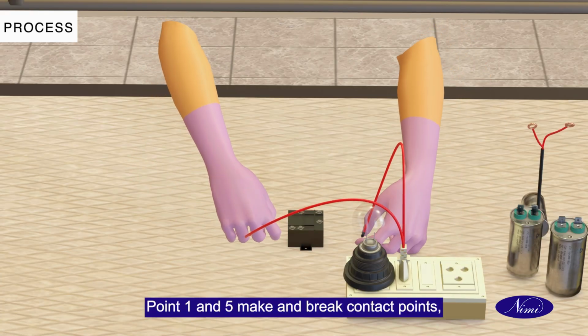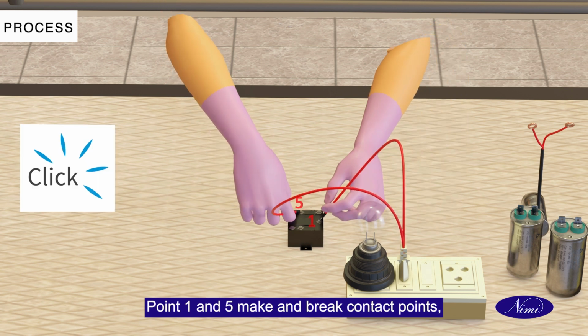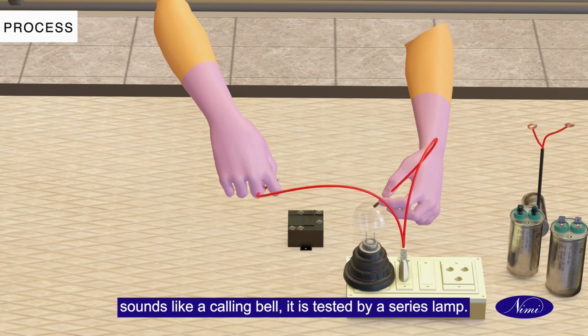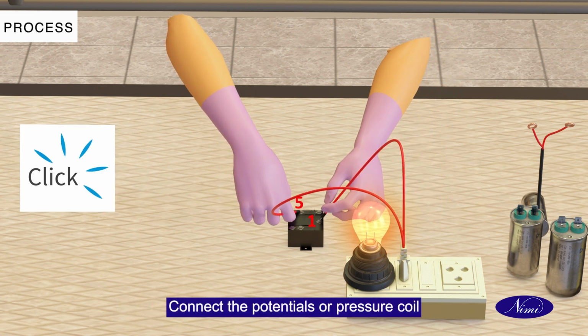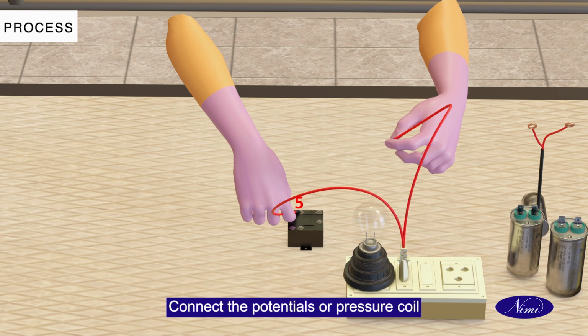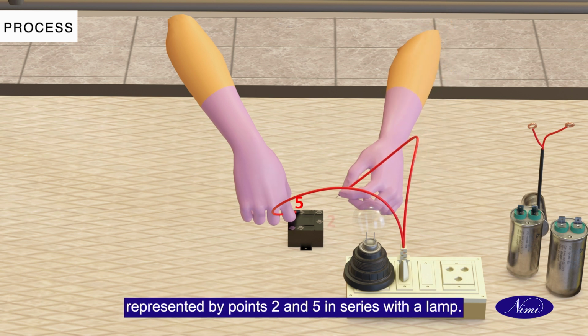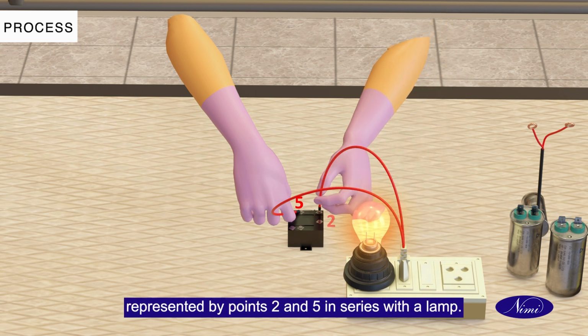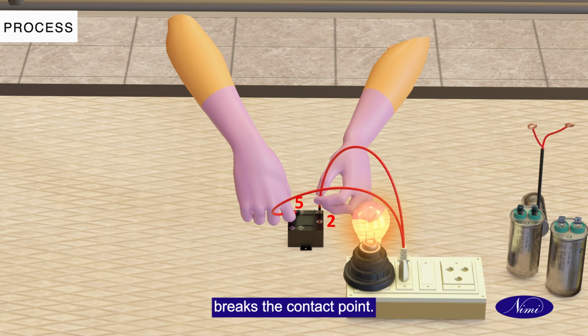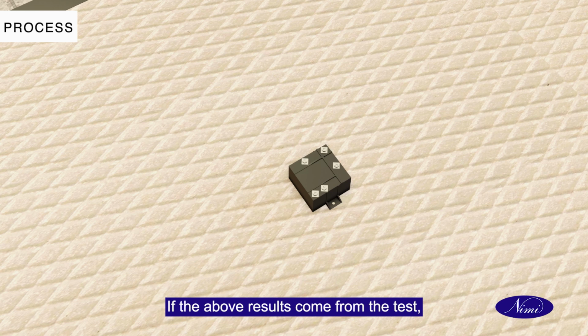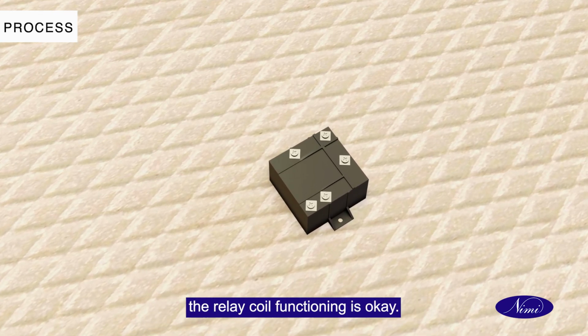Points 1 and 5 make and break contact, and sound like a calling bell. It is tested by a series lamp. Connect the potential or pressure coil, represented by points 2 and 5, in series with a lamp. If everything is in order, you should hear only one tick sound as it gets energized and breaks the contact point. If the above results come from the test, the relay coil functioning is OK.